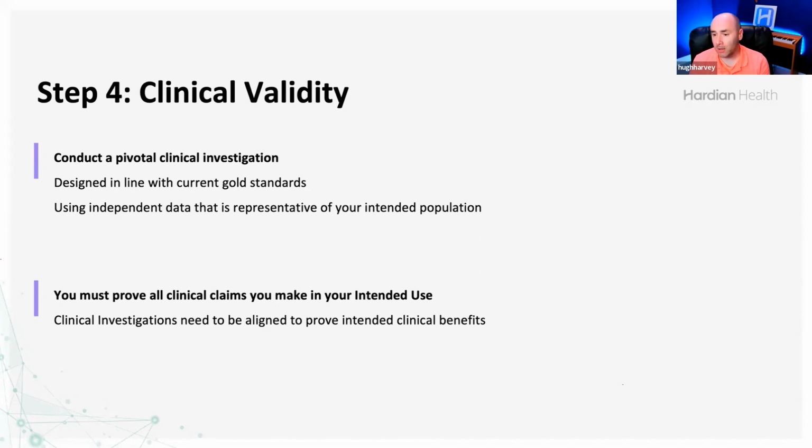Ali has asked, can synthetic data be used for bench tests? Yes, it can be, though you will obviously have to very transparently qualify and quantify the quality of that synthetic data and how relevant it is to your studies. We are seeing this increasingly as a topic, especially where there is data sparsity for certain types of medical products. It's a little bit controversial, and I wouldn't rely on your pivotal clinical investigation relying on synthetic data unless you can prove a very strong association with real world data.